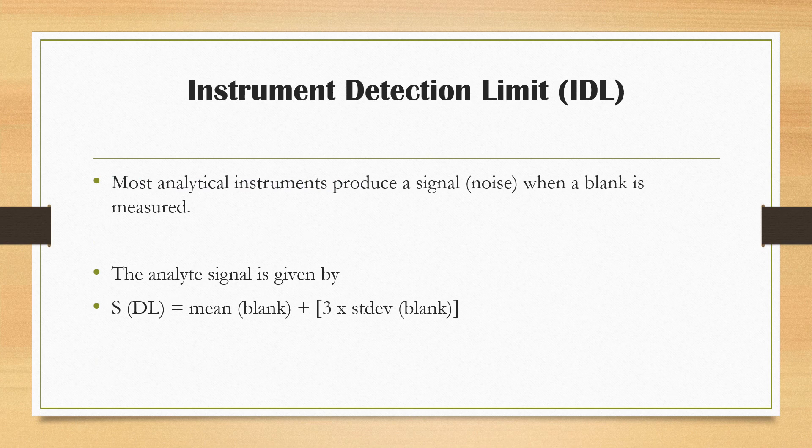When you run a sample, most analytical instruments will produce a signal which is associated with the sample you have measured. Likewise, when you run a blank solution, these analytical instruments also produce a signal or noise as a result of the blank solution. So from the blank solution that you run, you can calculate the detection limit of your instrument by finding the mean and the standard deviation of the blank solution.